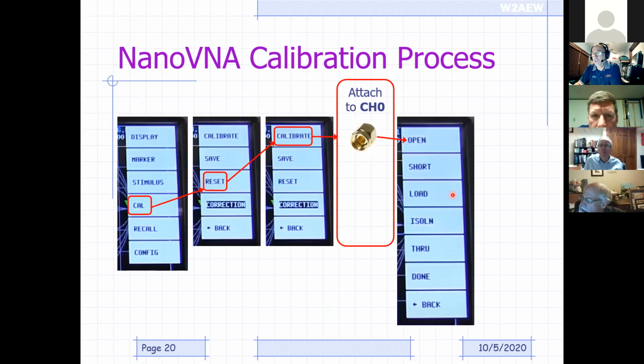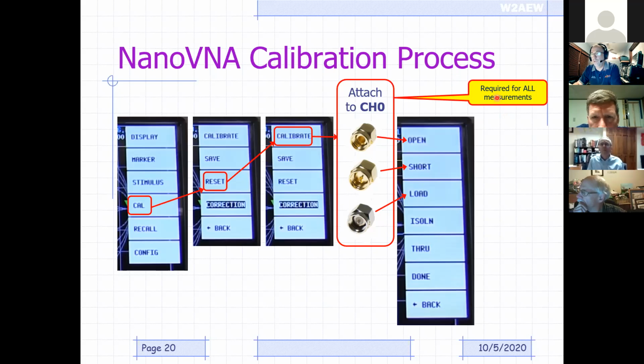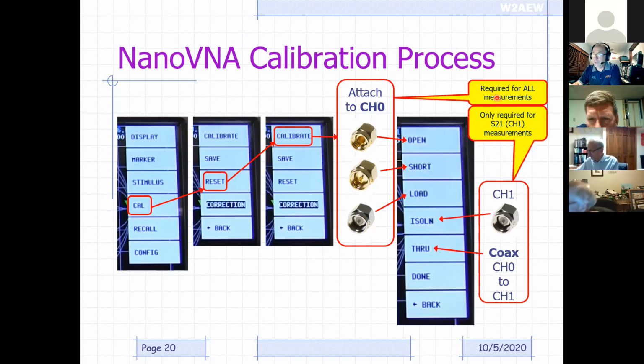And what this is prompting you for is to attach an open to channel 0. And then once you connect the open and touch that, it'll prompt you to add the short. Then it'll prompt you to add the load. Okay, and if you're only doing, again, the single port measurements, you could just hit done at that point. Again, because those are required for all the measurements. If you're going to be making transmission measurements of any sort to look at loss in a coax or whatever it might be, then you want to do the isolation and through measurements.